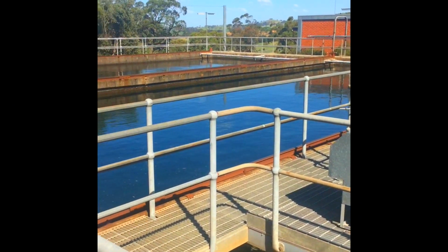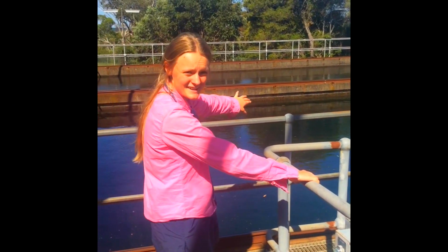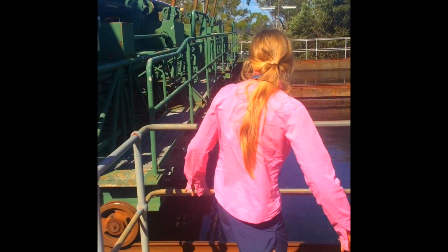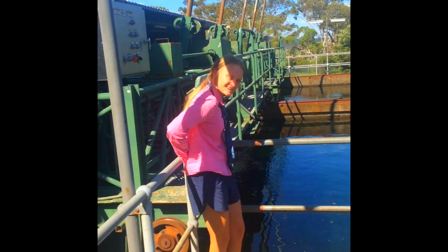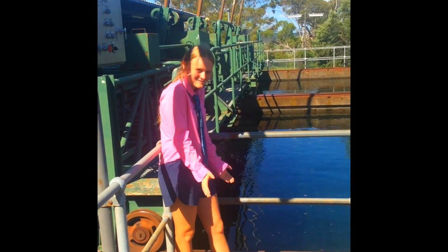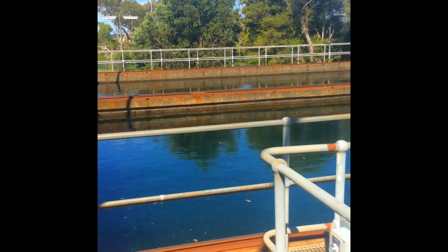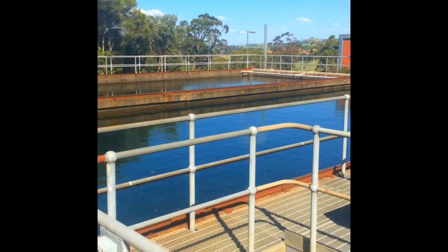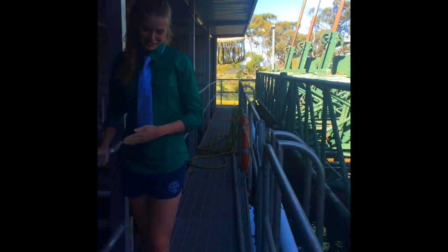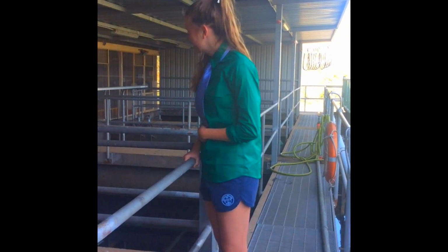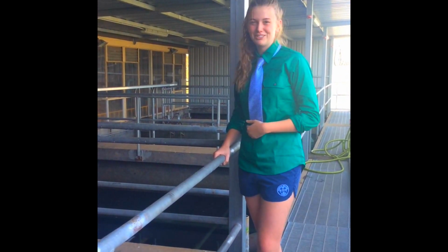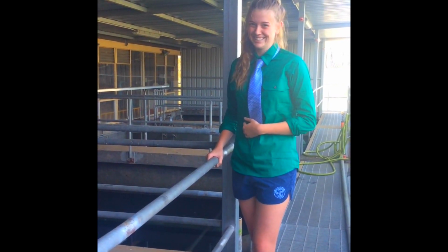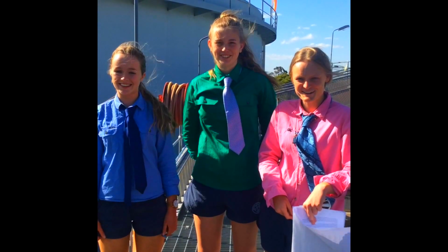Next up, sedimentation. The sediment is now called floc, and it drops to the bottom. Every 10 hours or so, these come along and scrape the bottom of these sedimentation tanks, taking with them all of the floc. Water then passes through this weir into the filtration tanks where it is polished through 3 layers of particles: coal, sand and garnet. Next, disinfection.